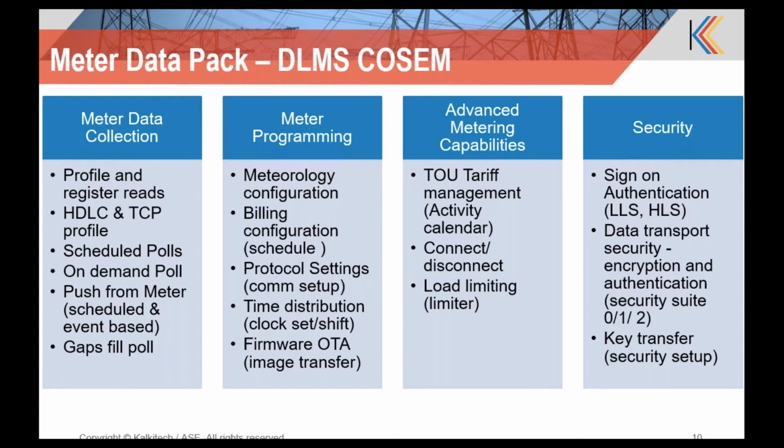That is by default supported in the meter data collection module. And the data can be collected on HDLC, that is a serial version of DLMS, as well as the TCP/IP profile of DLMS. And the IP connection can be on IPv4 as well as IPv6.